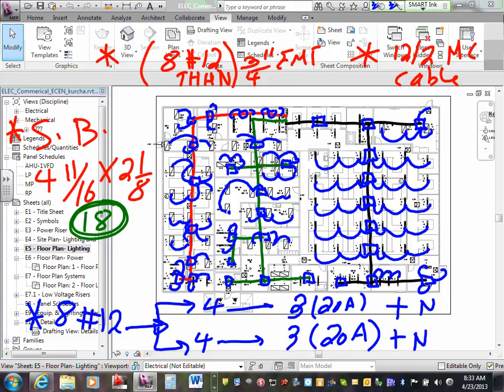Here's what I did. I took 3/4 of an inch. The red and the green and the black are my 3/4 of an inch. So I took a 3/4 of an inch from this side of the building and ran it all the way to the panel. Another 3/4 of an inch from this side of the building, the green, all the way to the panel, and a third 3/4 of an inch from this side of the building all the way to the panel. So I have three 3/4 of an inch conduits. Each of them can be loaded with 8 conductors number 12, or even more. Remember, the code says you can go up to 16. So if in this area this conduit at one time needs to carry 9 conductors, so be it.